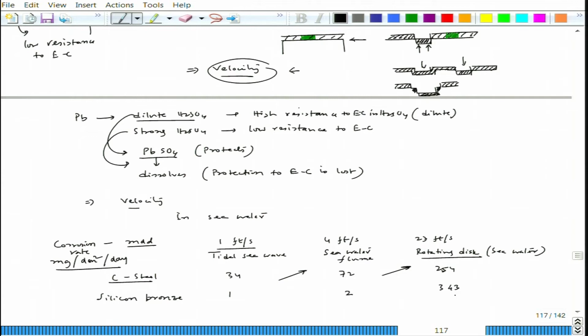Now, if we consider silicon bronze, at 1 feet per second the corrosion rate is 1 MDD, and then it is 2 MDD when it is 4 feet per second, and then it becomes quite a jump, 343 MDD. So, that is the kind of increase in erosion corrosion that happens once the speed increases beyond a critical limit.